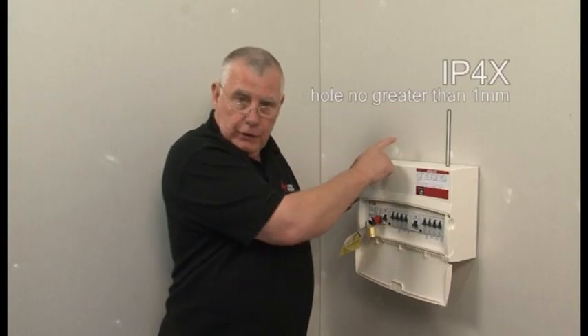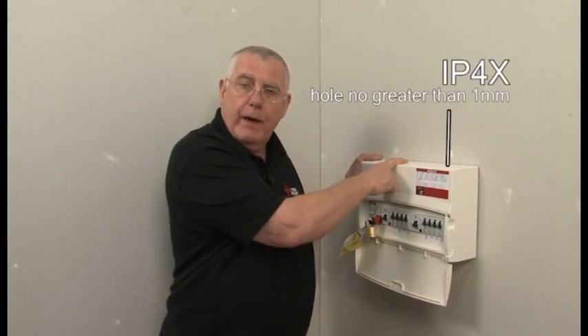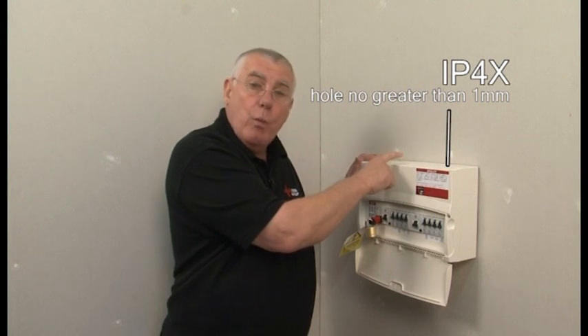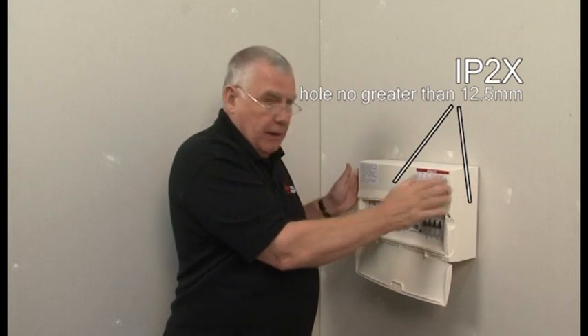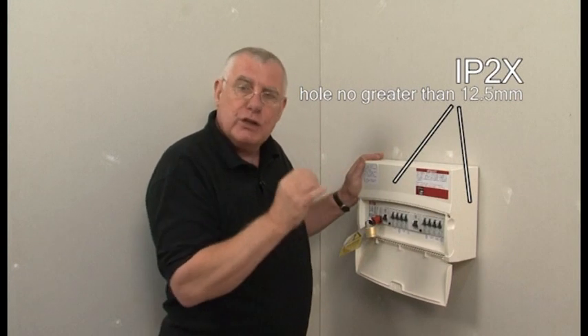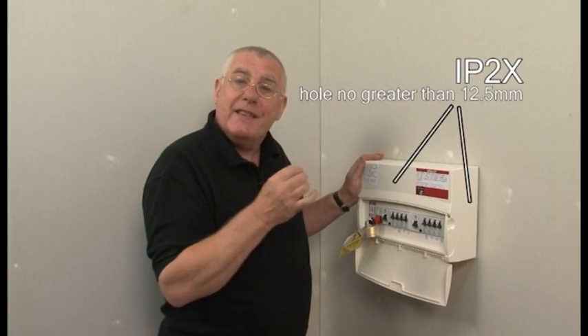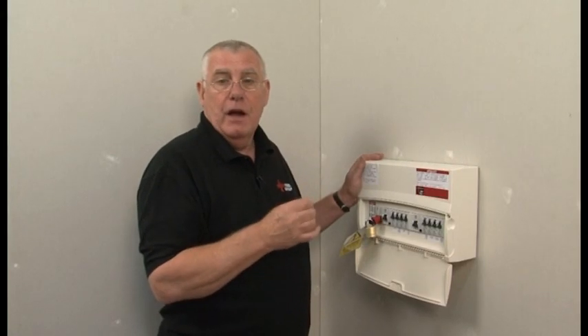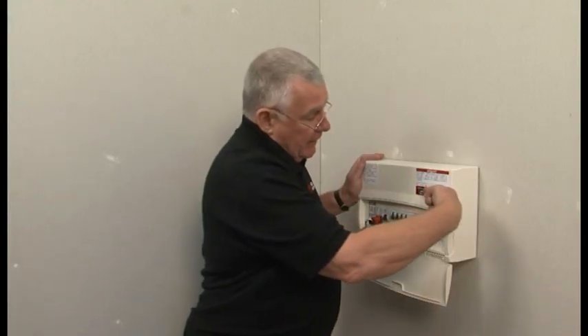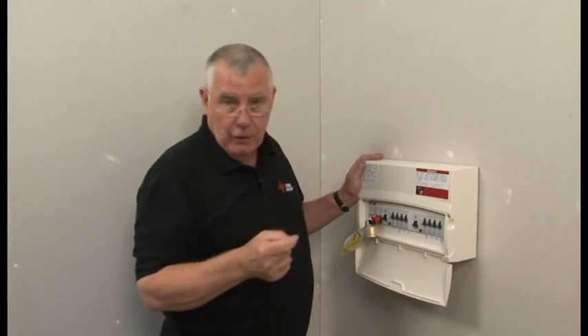It should be possible to confirm by thorough visual inspection that we have the necessary degree of protection against the ingress of fingers or other solid objects in any enclosure. For a domestic consumer unit, the top should be a minimum of IP4X, that's no holes bigger than 1mm, and the sides and the front should be a minimum of IP2X, that's no holes bigger than 12.5mm, and also no deeper than 80mm into the enclosure.